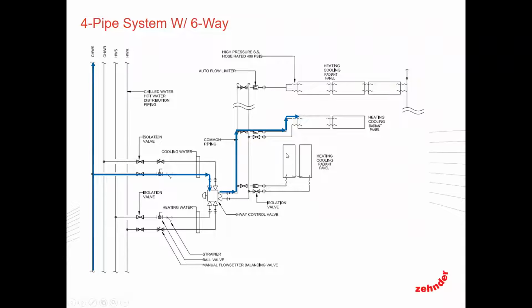Now on the right-hand side, I've got a couple different ways of piping the panels, so I don't want to focus too much on this, just on the actual piping itself. I'm going to talk more about options and piping and things of that nature later. So your 6-way valve will divert and allow your chilled water into your circuit, and then returns back into your chilled water return. On the heating side, the 6-way valve does the same thing, opens up and diverts into your circuit, and then returns your hot water back into your return water pipe.